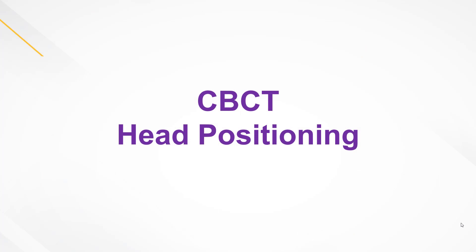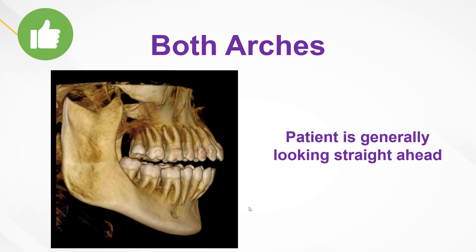Let's talk about head positioning. When positioning the patient, we want the arch being captured to be fairly parallel to the floor. When capturing both arches, I generally instruct the patient to look straight ahead. Here's an example of the patient looking straight ahead and how that translates to what you see on the CBCT. Usually, if the patient is looking straight ahead, the maxillary arch will be fairly parallel to the floor, while the mandibular arch is going to be angled down a little bit due to the curve of Spee. You could have both arches a little more balanced by raising the chin up slightly, but that gets too granular — looking straight ahead is totally fine.